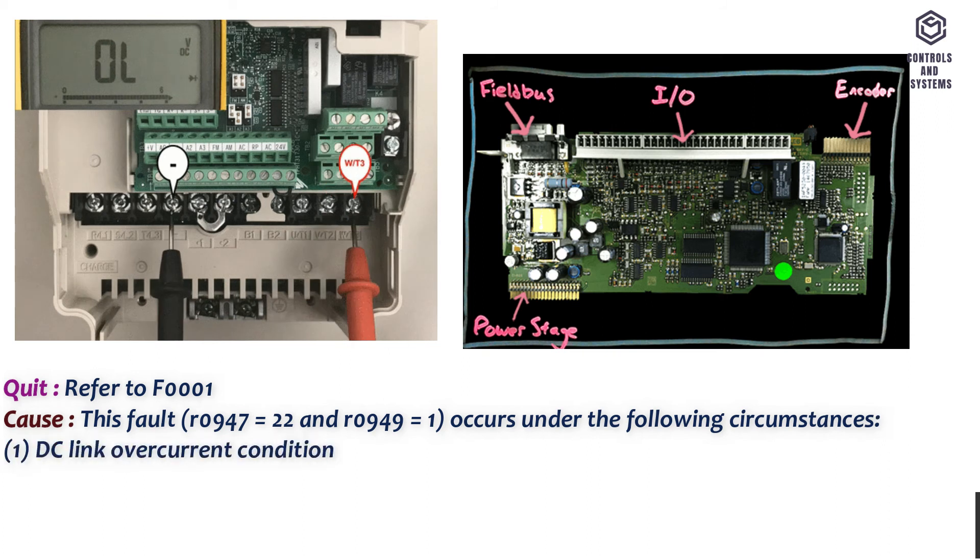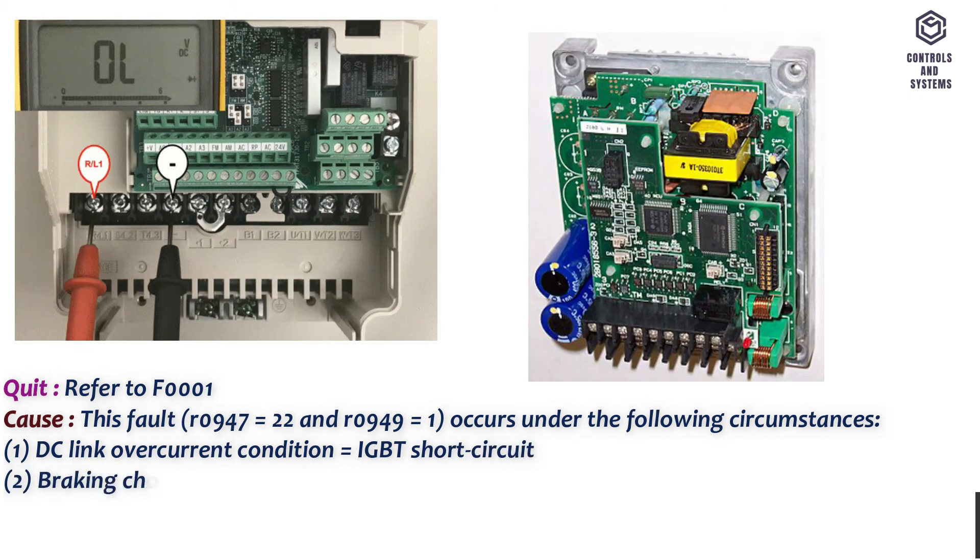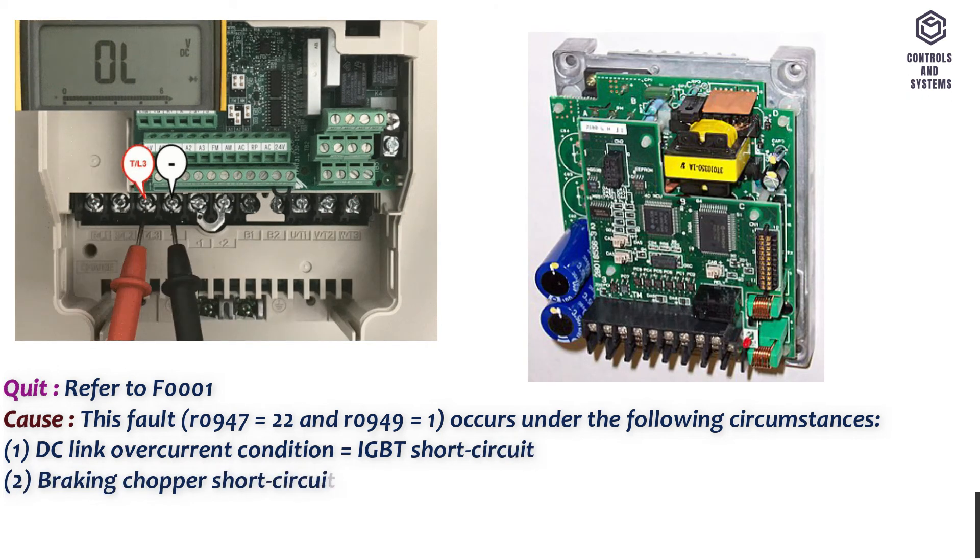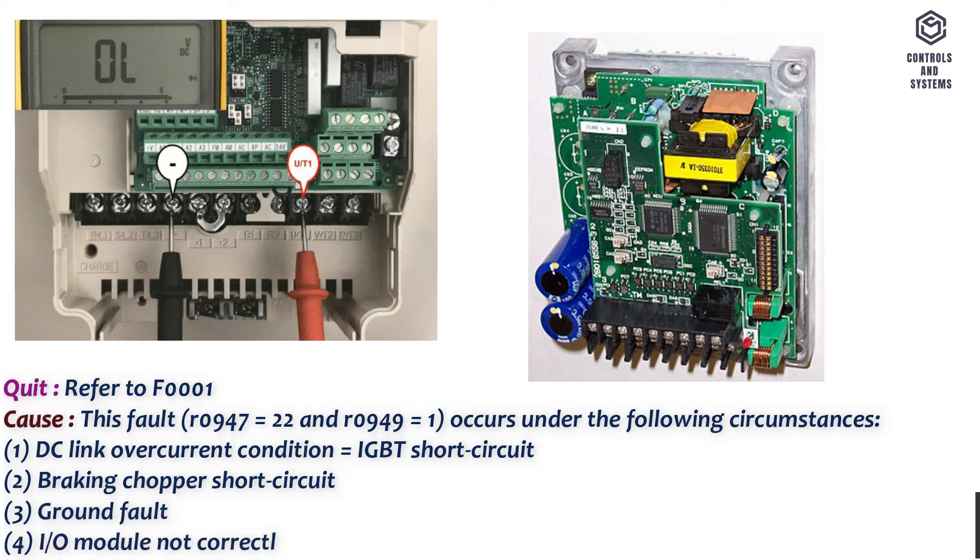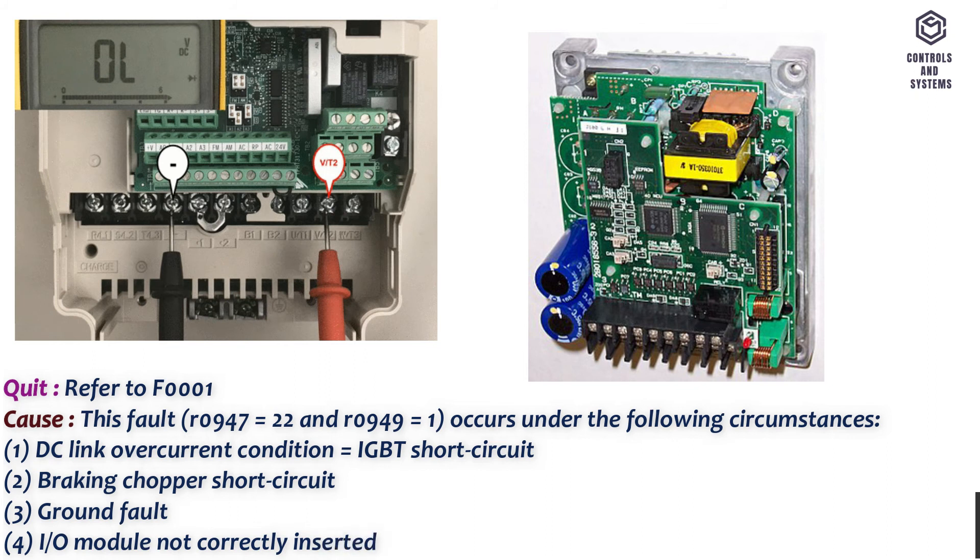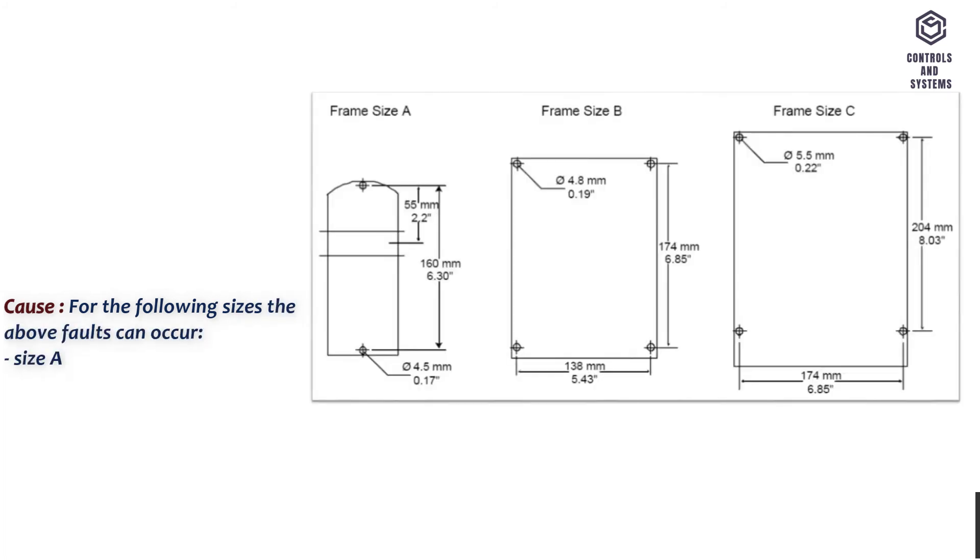1. DC link overcurrent condition equals IGBT short circuit. 2. Braking chopper short circuit. 3. Ground fault. 4. IO module not correctly inserted. For the following sizes the above faults can occur: Size A to C: 1, 2, 3, 4.